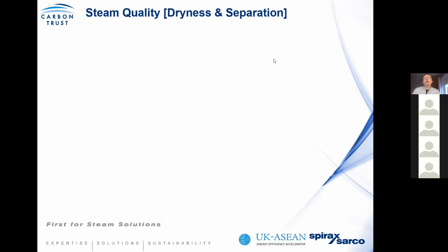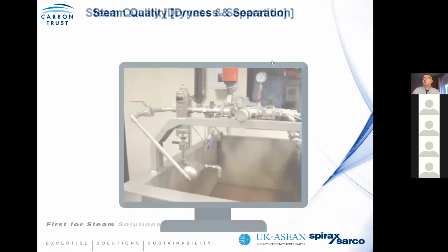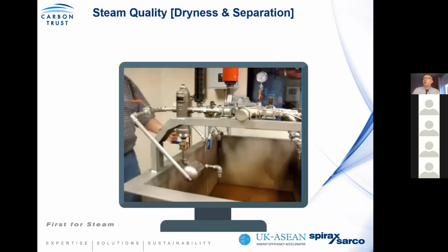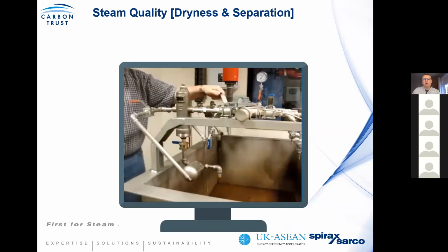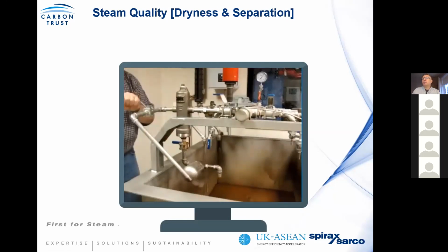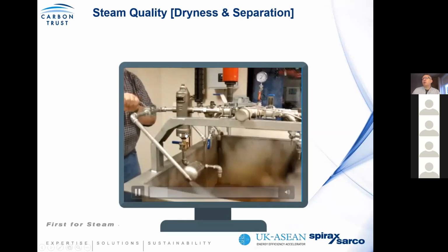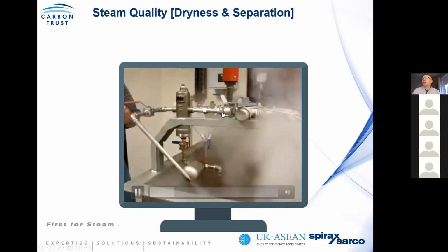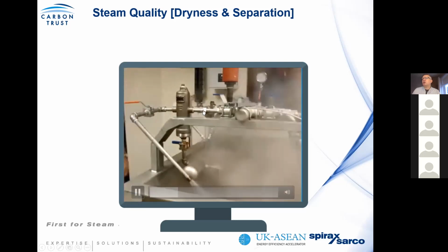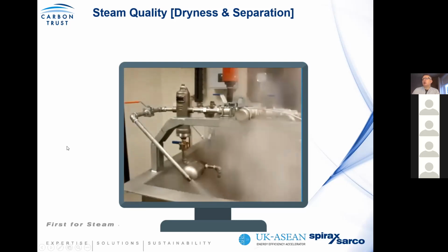Now, what I want to demonstrate here is, please understand, this is a laboratory condition. It was done to demonstrate the effect of wet steam. Please do not copy this within your process, because this was done under controlled conditions to basically demonstrate what wet steam is. So what we have here is a test lab in one of our offices, where we're showing what a separator is and the impact on the operation of the separator. So this is your separator here. And you can see in this condition that we're controlling the discharge of steam, but we are not allowing the condensate to be removed effectively by the separator.